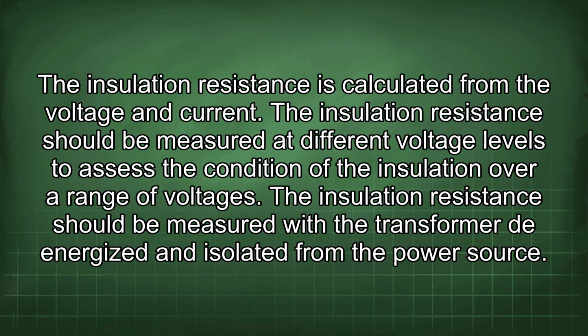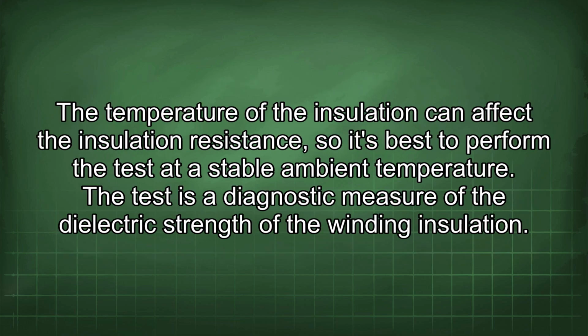The insulation resistance should be measured at different voltage levels to assess the condition of the insulation over a range of voltages. The insulation resistance should be measured with the transformer de-energized and isolated from the power source. The temperature of the insulation can affect the insulation resistance, so it's best to perform the test at a stable ambient temperature. The test is a diagnostic measure of the dielectric strength of the winding insulation.